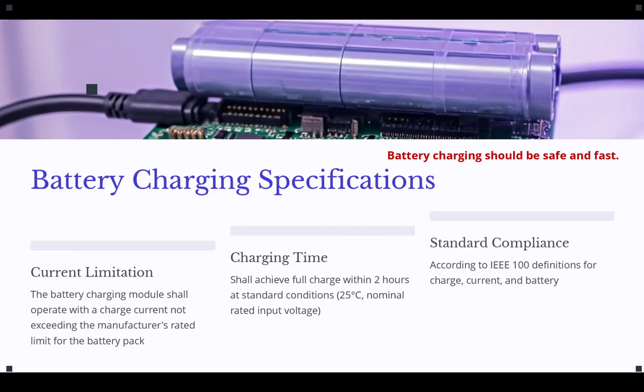For charging time, that device shall achieve full charge within a specific time with a specific unit, 2 hours. At what? At a standard condition, which means 25 degrees Celsius, at nominal rated input voltage. So if the input voltage is different, that's not 2 hours. If the temperature of environment is different, not 2 hours. And it should be all those definitions of charge, full charge, nominal rated voltage, charge current, all of them are defined in IEEE 100.